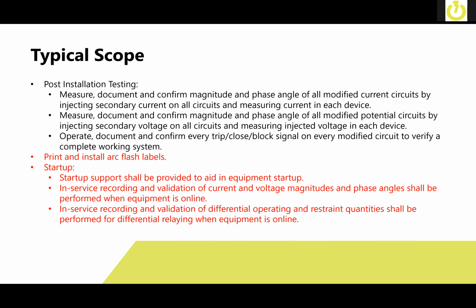And then operate, document, and confirm every trip, close, block signal on all modified circuits to verify a complete working system. For instance, you may have a single contact that you modified in the trip circuit, but that device may be daisy chained onto other multiple devices. If you don't test the entire chain, you may not realize that you inadvertently disconnected those other devices in the system until it comes time to trip, and it may not trip like it's supposed to.